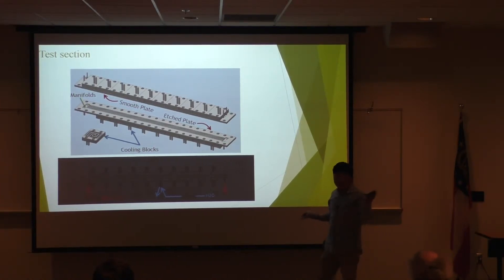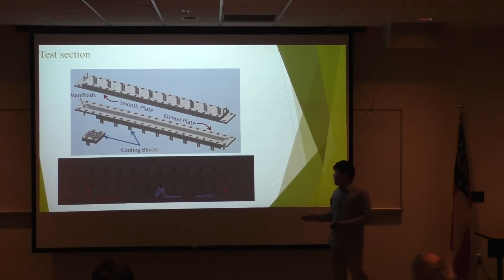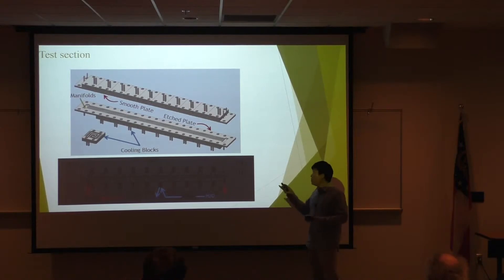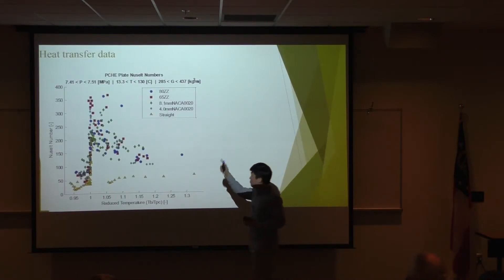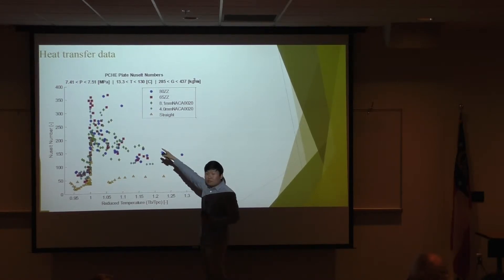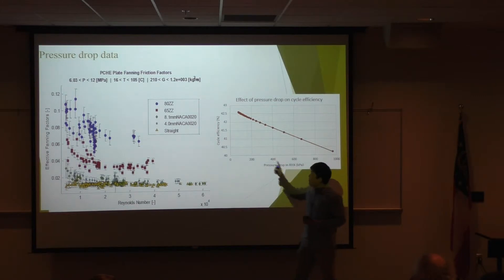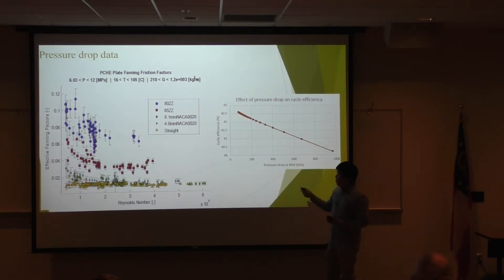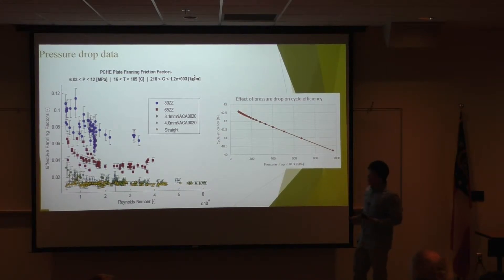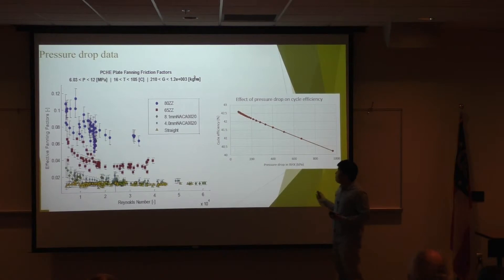This temperature information is very important to size the heat exchanger properly. If you make the heat exchanger very long, you will have enough length to transfer heat, but we also need to think about manufacturing cost and material cost. Based on that experiment, we can calculate heat transfer rate. For the zigzag channel, it has the highest heat transfer rate; straight channel is at the bottom; and airfoil is between them. But zigzag also has the highest pressure loss, which directly affects cycle efficiency — as pressure drop increases, cycle efficiency drops.